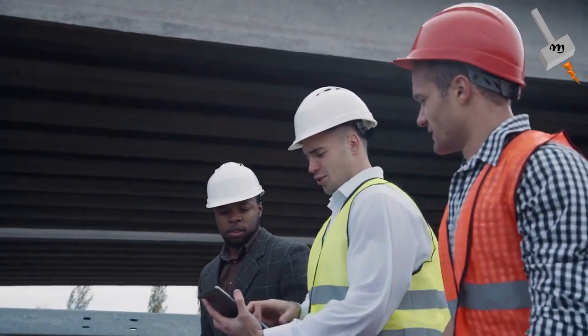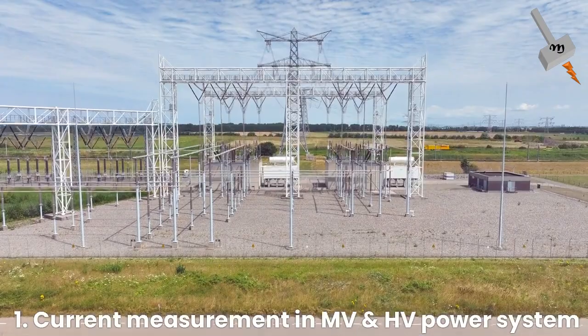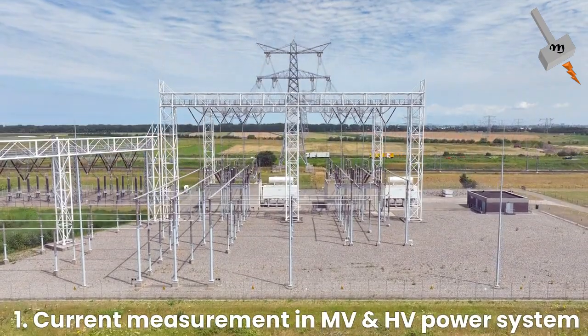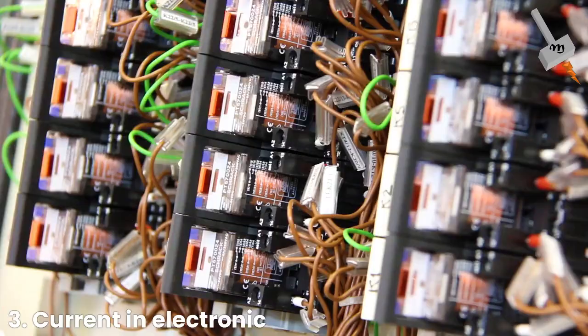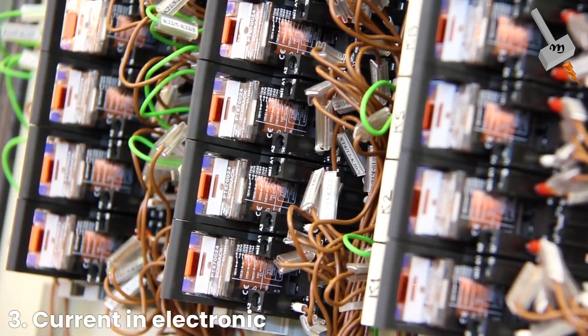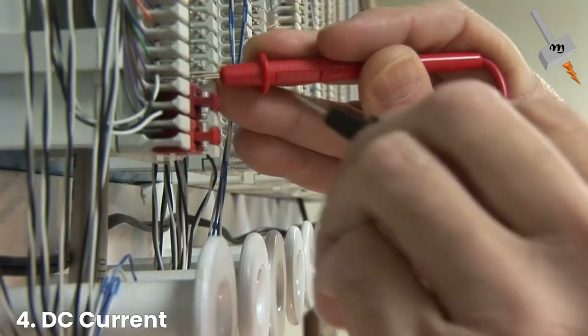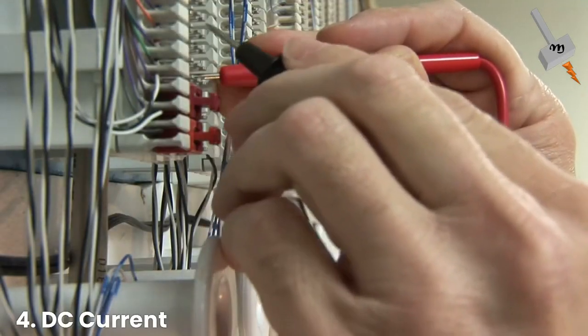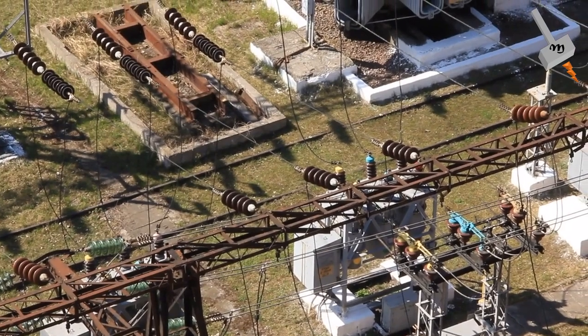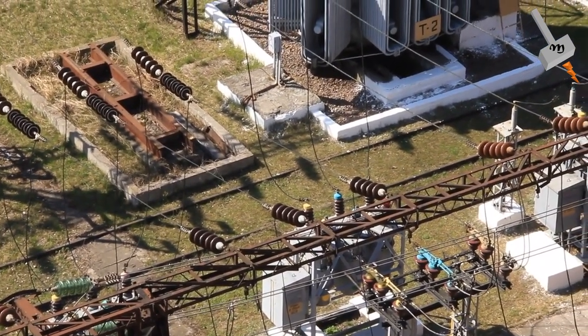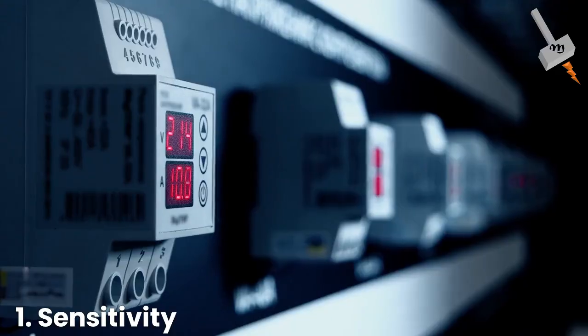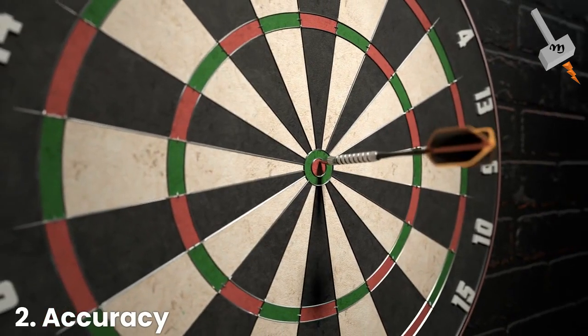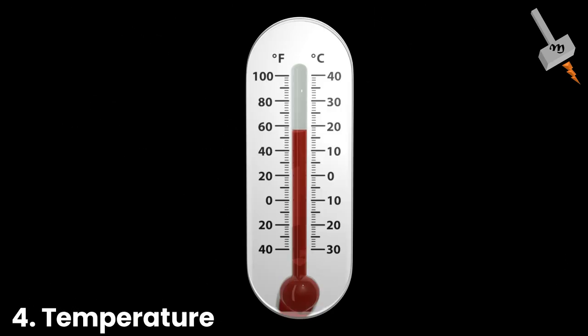So the need can be measurement of AC current in medium voltage or high voltage systems, high frequency current like harmonics, fault current, AC current in low voltage systems like electronics, or DC current. Here one point to be noted that, apart from the magnitude and type of current, some other factors also decide the selection of current sensors, like sensitivity, accuracy, linearity, temperature effect, interference, and bandwidth.